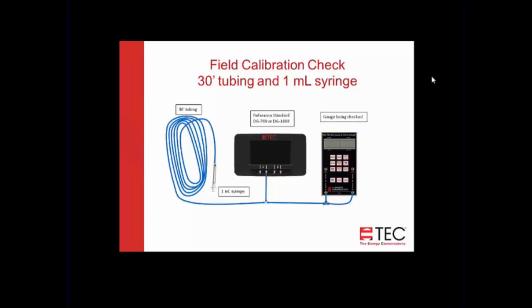One other thing that's interesting about this process is when you have a closed system like this, it's really susceptible to pressure changes. So if you wrap your hands around that tubing, for example, you'll see those pressures go way down. So you need to be cognizant of that, and you'll want to set everything up on a table and let it sit for a while for the tubing to adjust to the temperature on that table in that location, so the pressures will stabilize.